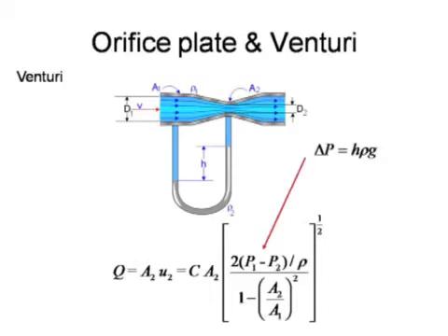Of course we can now substitute in for P1 minus P2, the pressure difference, and we can substitute in the equation depth times density, the static head equation. If we do that, we can then cancel the density terms out, but that sort of hides the secret, because bearing in mind the density in the square brackets has come from Bernoulli's equation, that's the density of the process fluid, the fluid flowing through the venturi or the orifice plate.